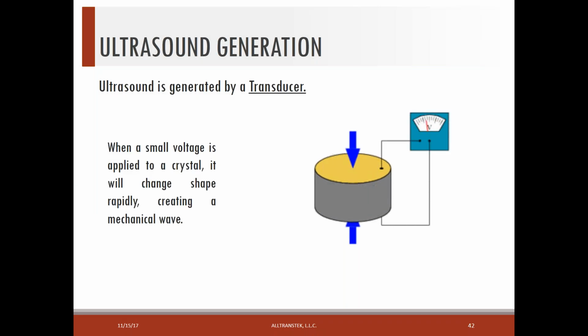And kind of how they work is that inside that transducer, if you apply a small voltage to it - it could be from a battery inside the unit, the UT meter - it will actually make that crystal expand and contract a million times a second. These vibrations can be used to put sound into the part. It creates like a mechanical wave.